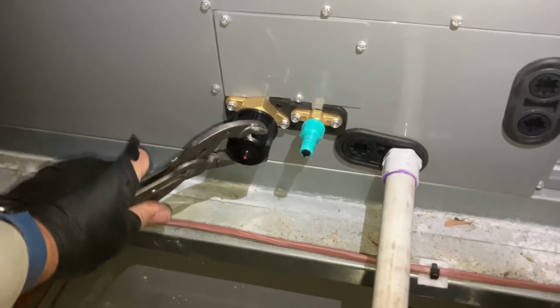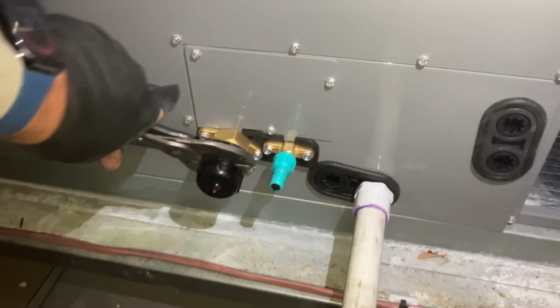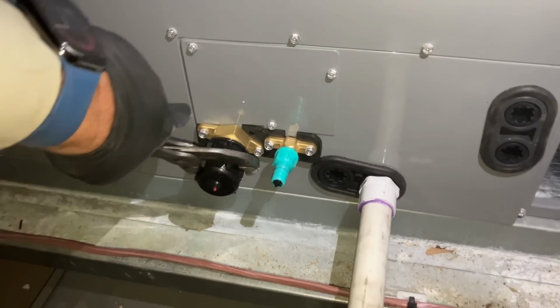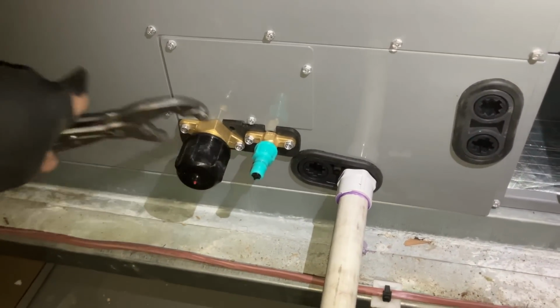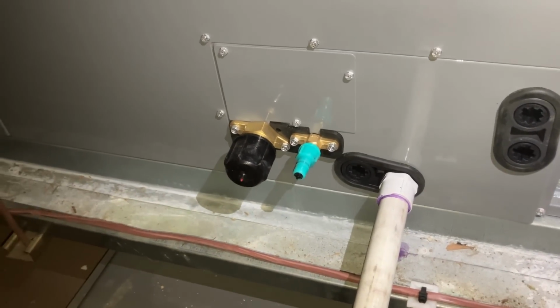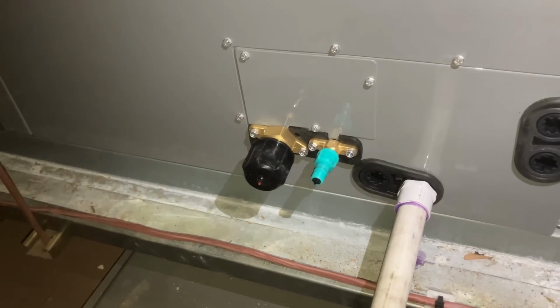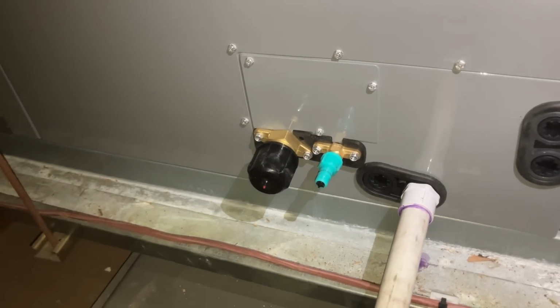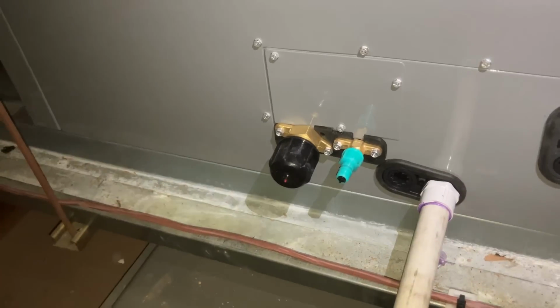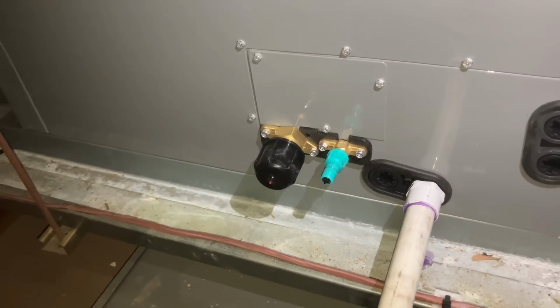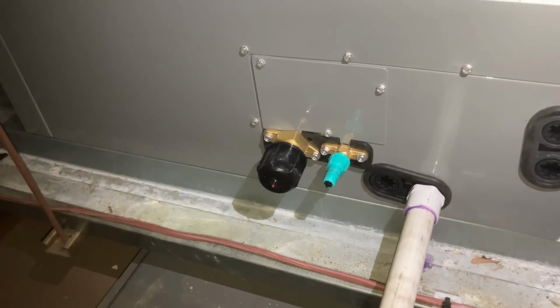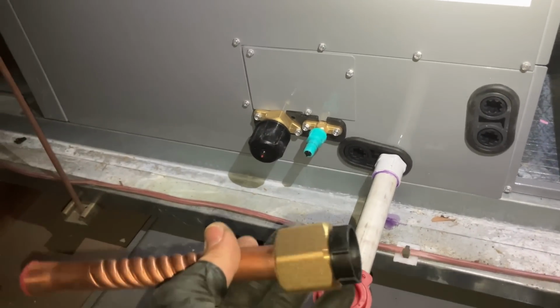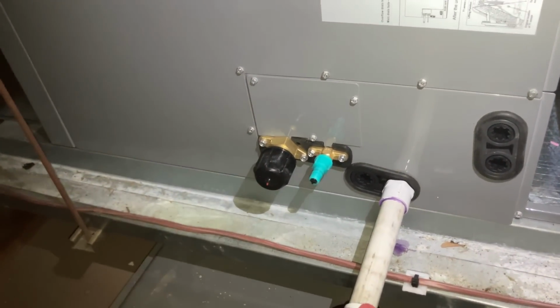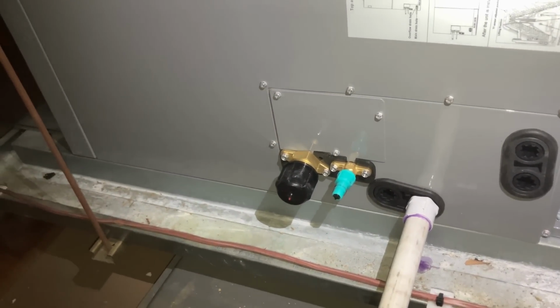All right, I cracked open my plastic cover on the 7/8. We have that nice nitrogen charge in the evaporator, so no damage during shipping. Nicey nice. And let that discharge that high pressure, and then hook up our factory supplied flare connection union to our evaporator.